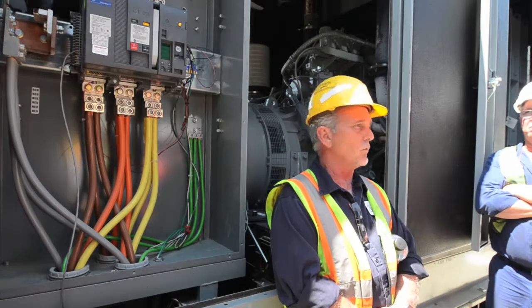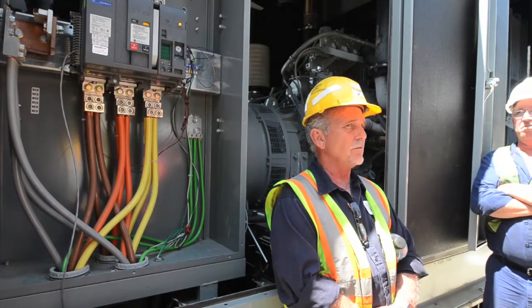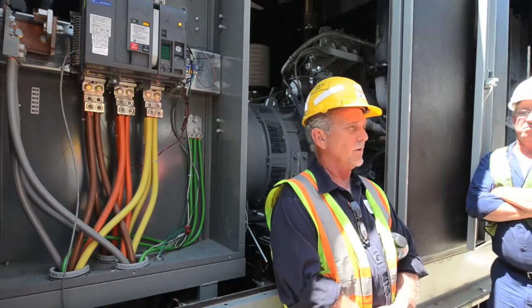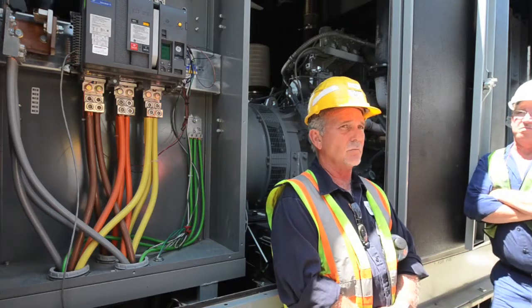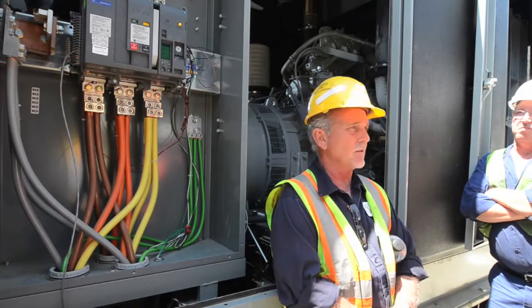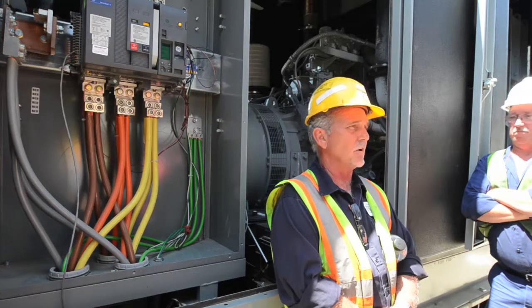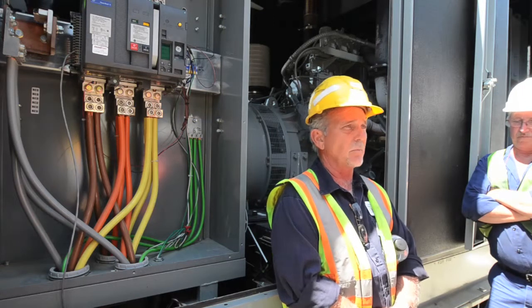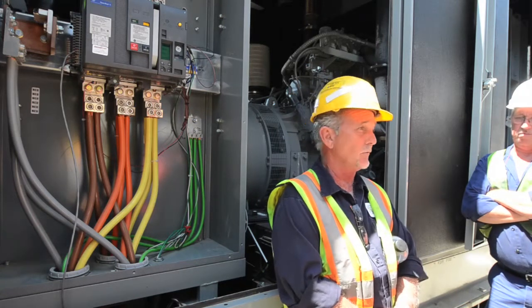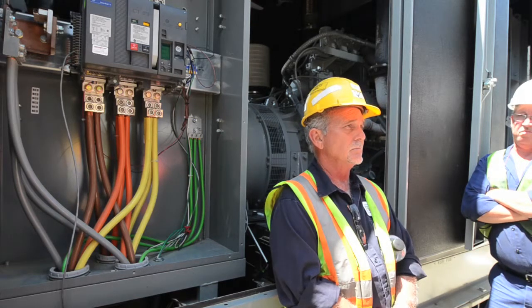But when you hit the run button, it won't close the breaker. So you'll be able to verify oil pressures and things like that, but you won't see any amperage out at all. That's a safety I actually programmed into here: when you hit the run button, you're not getting them to go online.